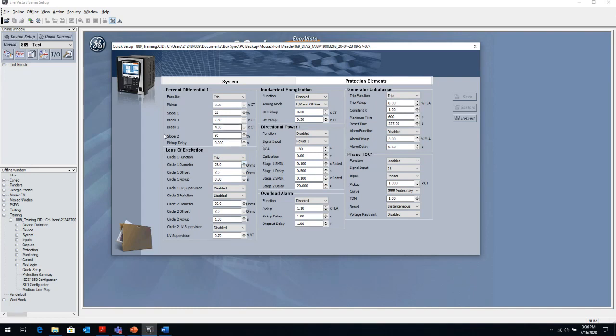And the loss of excitation, all the settings available with the loss of excitation, I mentioned the 2 offset circles, circle 1, circle 2, and then the 2 time delays associated with those 2 offset circles. So as you can see, in my case, I have the shorter, inner circle set up with a shorter time delay, and the outer circle set up with a longer time delay. I don't have the inadvertent energization enabled, so that's why it's disabled. To enable it, all I have to do is hit trip and hit save and basically enable the inadvertent energization. And these are my basic settings for the inadvertent energization.